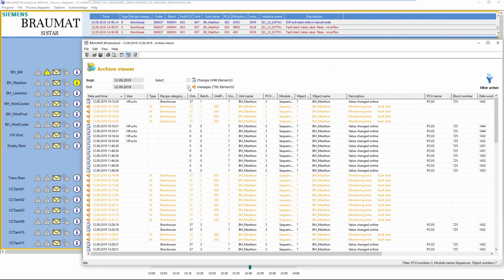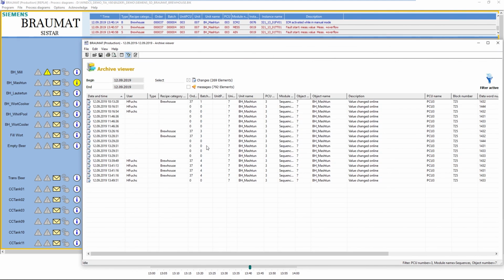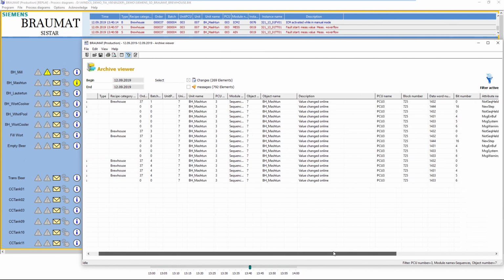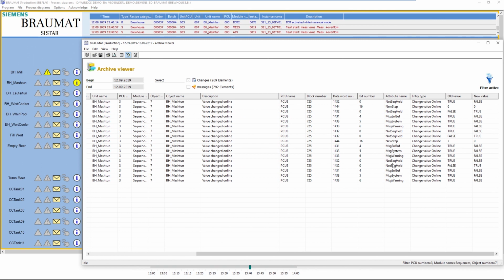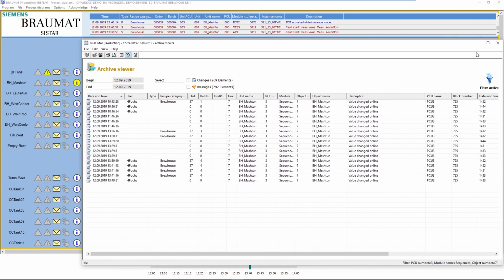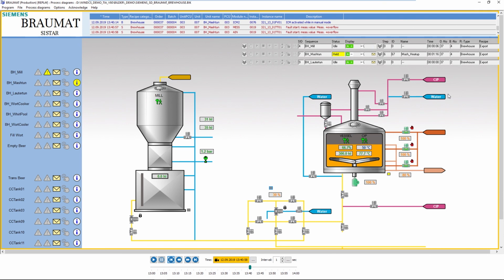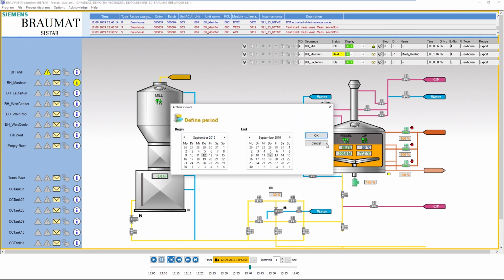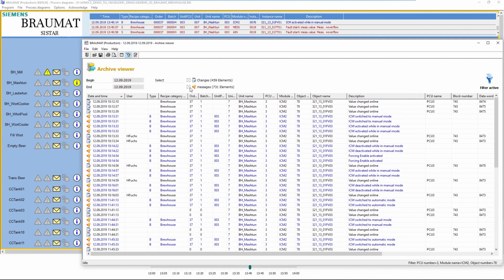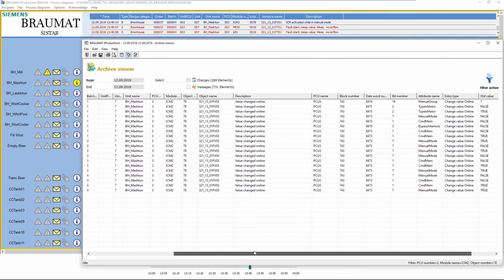This time, it is not the messages that are relevant for me, but the so-called changelog entries. Each operation is entered here in a log file with a record of the corresponding user, the aggregate, i.e. the mash tun, and the attribute that has been manipulated. In fact, one operator, Horst Fuchs in this case, did the manipulations. You can practically ask him if he can still remember. What is also noticeable is that the steam valves here are set to manual. I will also get this presented in this changelog, with the entry user, valve tag name, and which attribute did get manipulated.